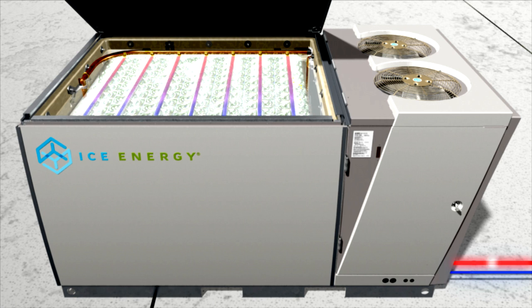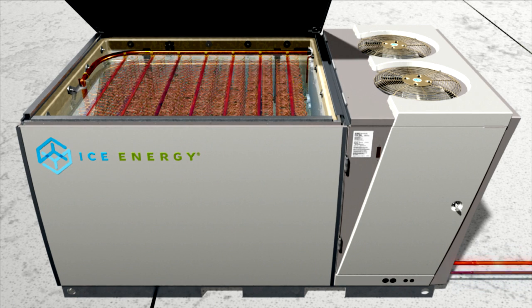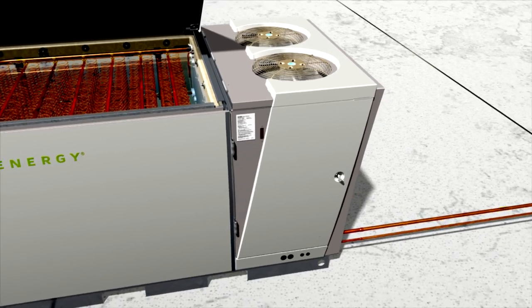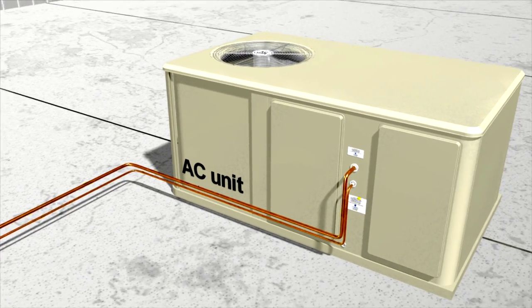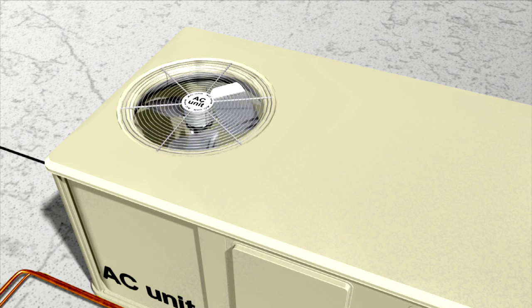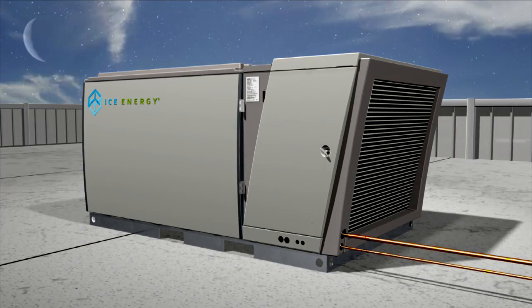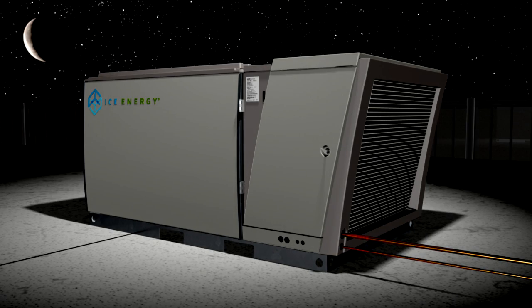The cooling cycle lasts for up to six hours while the ice slowly melts. When the ice is fully melted, the IceBear transfers the job of cooling back to the building's AC unit to provide cooling as needed until the next day. During the cool of the night, the Ice Charge mode is activated and the entire cycle begins again.